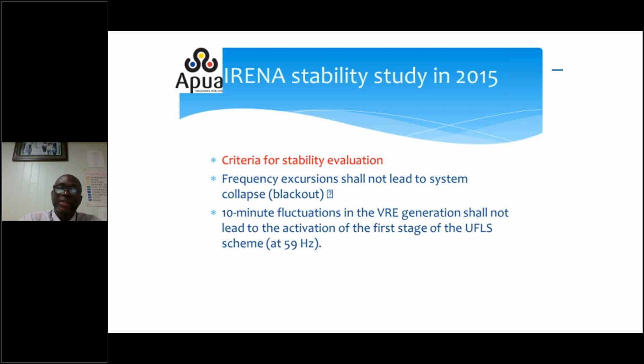The criteria that IRENA used in the study, they wanted to ensure that the frequency excursion shall not lead to system collapse. That is very crucial. And they were looking at a 10-minute fluctuation in VRE. Now, that is more towards the stability and steady state. They didn't look so much on the transient side. Transient, you look at fractions of a second. The dynamic, you more look at the seconds, and steady state, more minutes. Next slide, please.